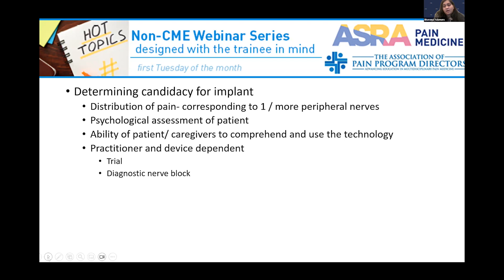Next slide. So if you look at this, you can see in yellow that this is just a diagrammatic representation where the yellow is the nerve. Above it, the lead is implanted with the receiver, the electrode end, which is tied closer to the nerve, and the receiver end, which is subcutaneous. So I'm just going to go over the basic principles of implanting these devices, because the approach is going to be very different when you do an axillary or a suprascapular versus doing a genicular or an ilioinguinal. Each of those is going to be very dependent on the ultrasonographic picture with which you're going to place the device.